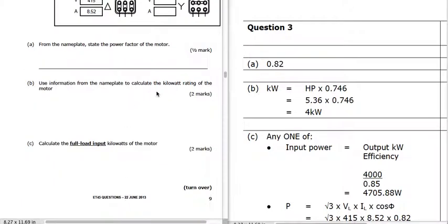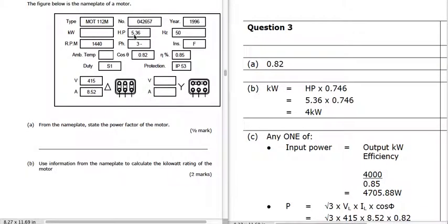Use the information from the nameplate to calculate the kilowatt rating of the motor. It's an old-style motor with HP — horsepower — of 5.36. The kilowatts is going to be the horsepower times 0.746. This 0.746 is a fixed conversion value from horsepower to kilowatts, and that gives us 4 kilowatts.